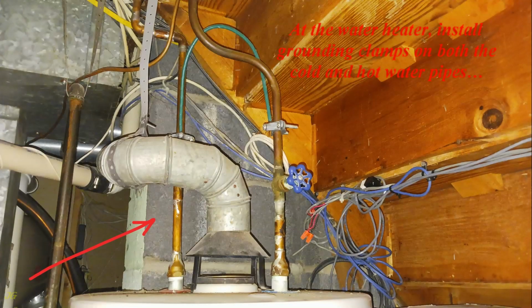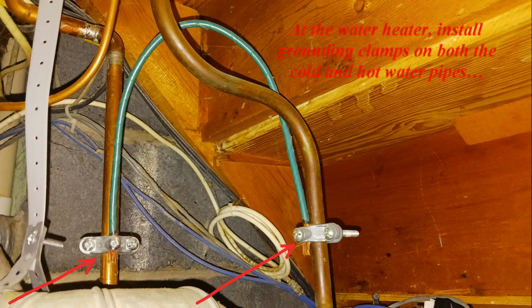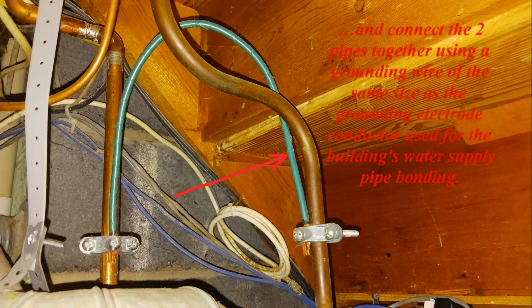At the water heater, install grounding clamps on both the cold and hot water pipes, and connect the two pipes together using a grounding wire of the same size as the grounding electrode conductor used for the building's water supply pipe bonding.